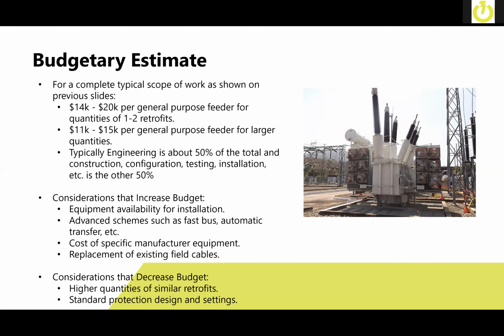From a budgetary estimate standpoint, for a complete typical scope of work as shown on the previous slides, for a general purpose overcurrent type feeder that's feeding maybe a transformer or a motor, etc., you're looking at around $14,000 to $20,000, depending on the complexity, for small quantities of 1 or 2.